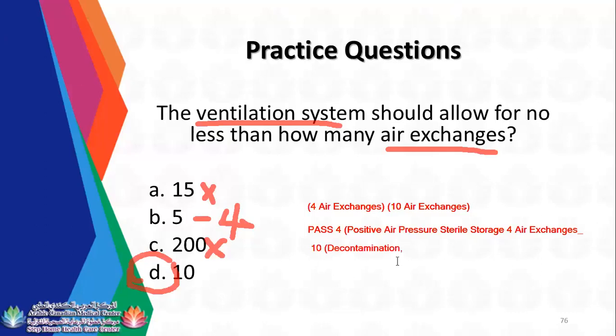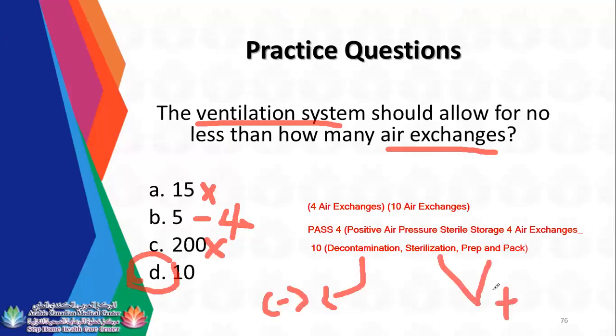What else? Sterilization area and prep and pack. But your decontamination has a different air pressure - for decontamination this is negative. For sterile storage, prep and pack, and sterilization, this is positive air pressure. So the purpose of negative is the bacteria cannot escape, cannot go out of the decontamination room to contaminate other rooms. Your prep and pack and sterilization has a positive airflow, which means bacteria cannot enter CSSD.